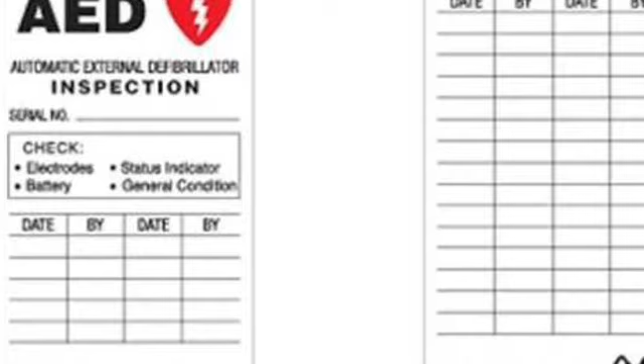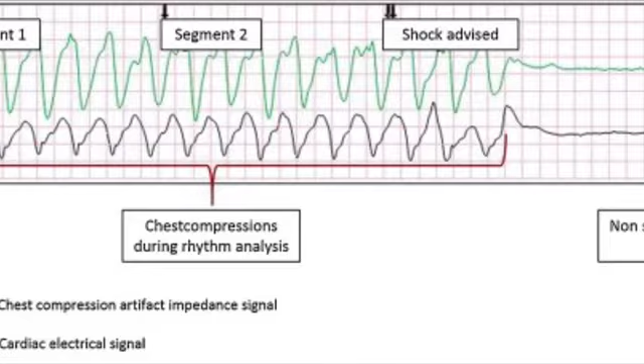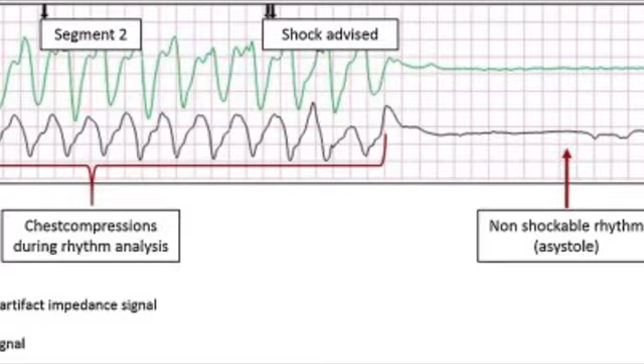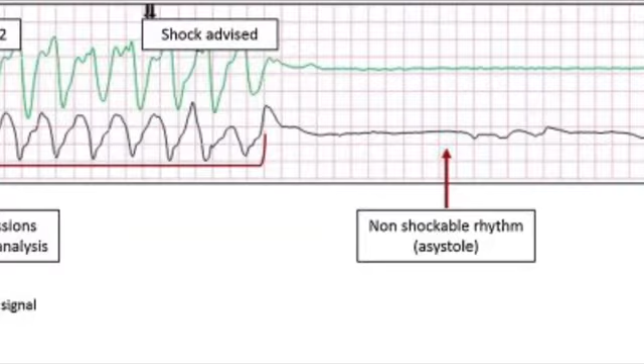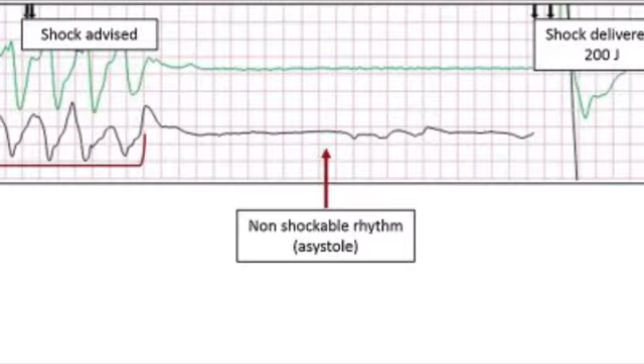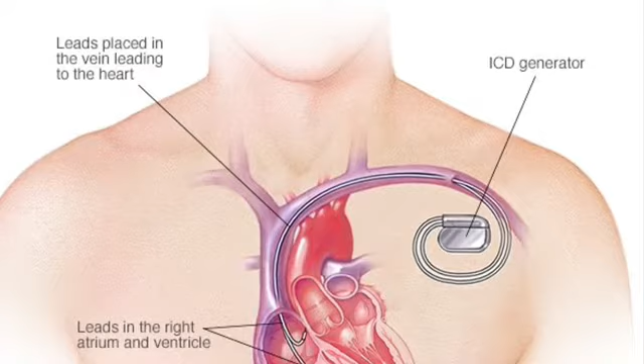Another thing about the AED is it has an internal memory that records when we're using it. There is a device inside for quality assurance that we can download after use, so we can see what the person's rhythm was, and we can also see when the person was shocked and how many times they were shocked. Some people even have implanted AEDs and implanted pacemakers, and the AED would pick up on that in the internal memory. We'll talk more about the implanted devices, or we can talk about them right now.